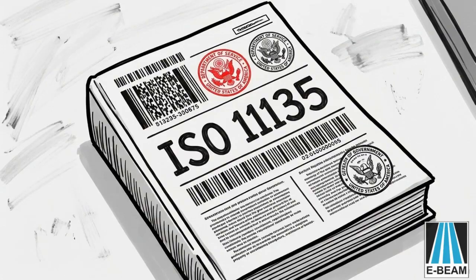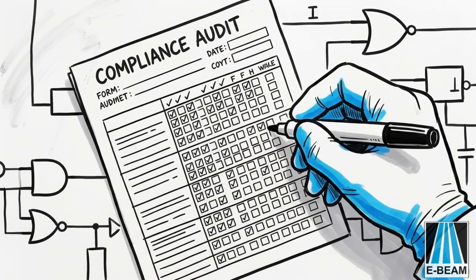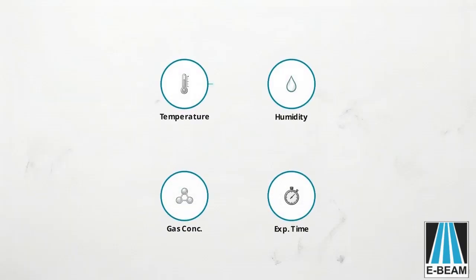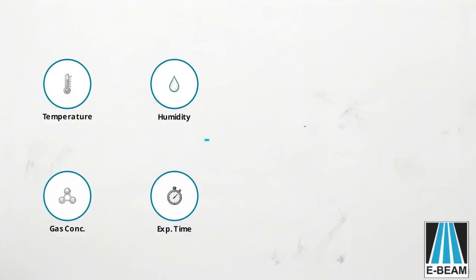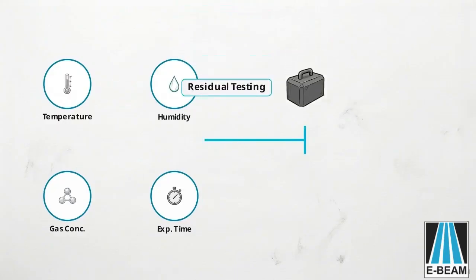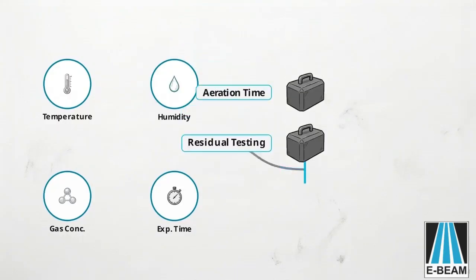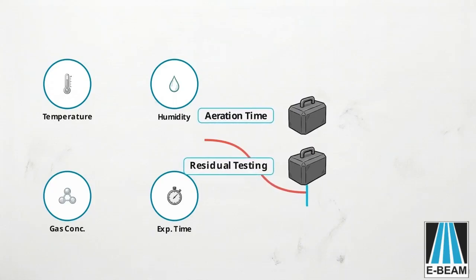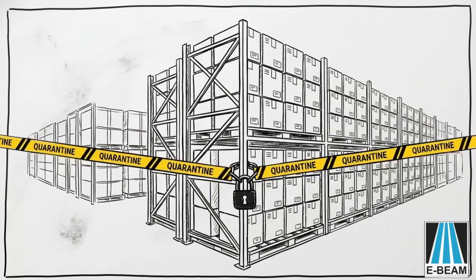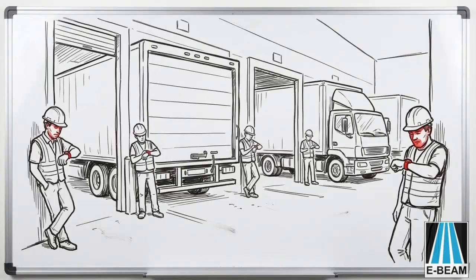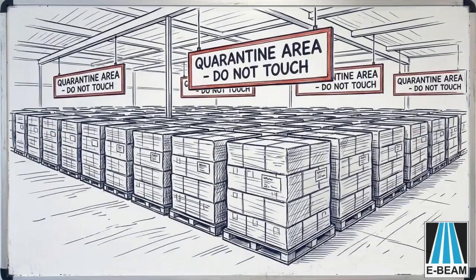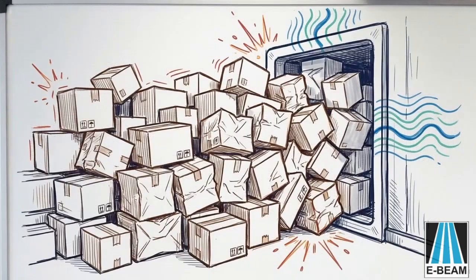EtO sterilization is governed by ISO 11135, and it's a multivariable process. You're managing temperature, humidity, gas concentration, and exposure time, all at once. And when the cycle is done, you're not done. You still need residual testing and aeration time before the product can be released. For many teams, that complexity adds up to longer timelines and less flexibility, especially when EtO capacity is tight.